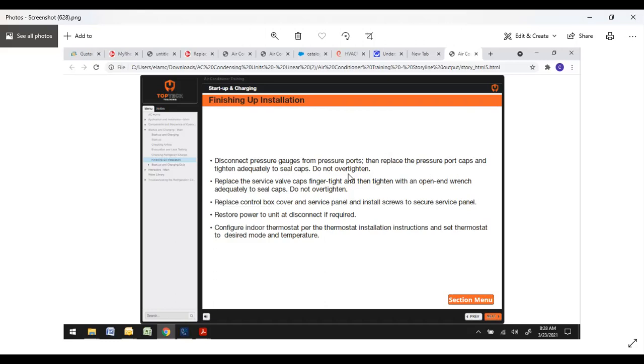Don't put leak lock and all that stuff on there. You shouldn't need to do that. Replace the service valve caps, finger tight. Some of them have a wrench in where you can tighten them up. Don't over tighten them. You don't have to put too much torque on them.